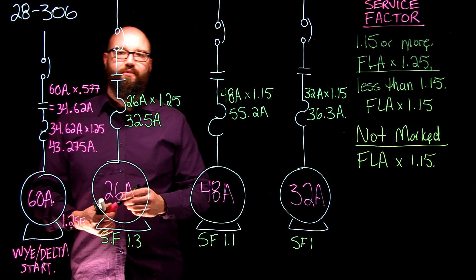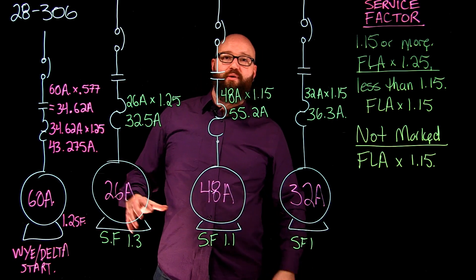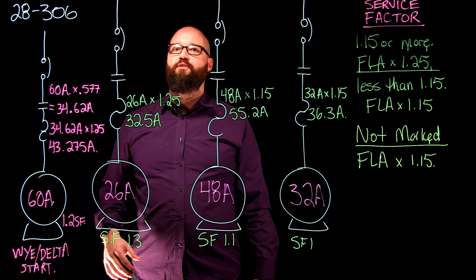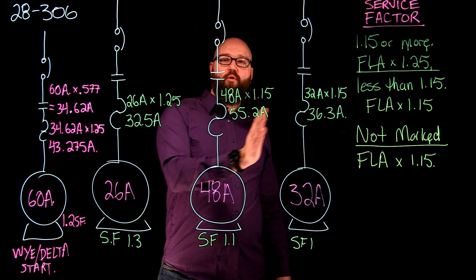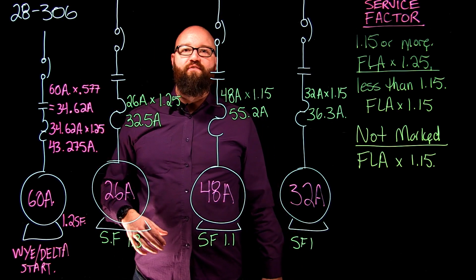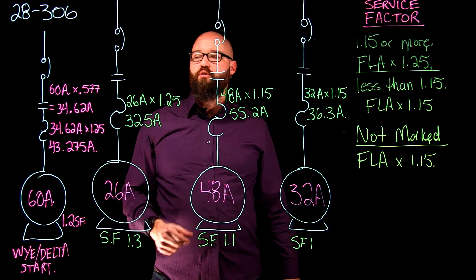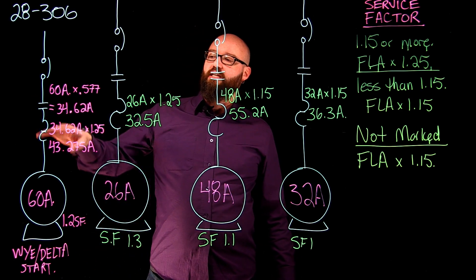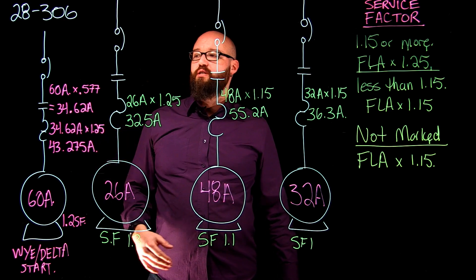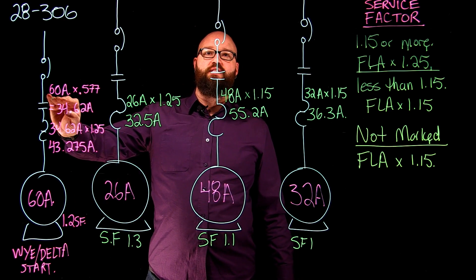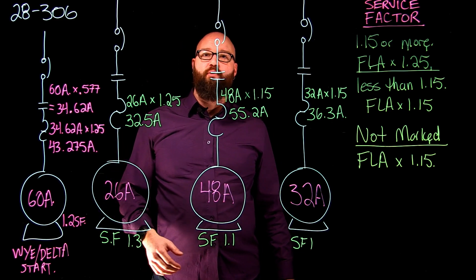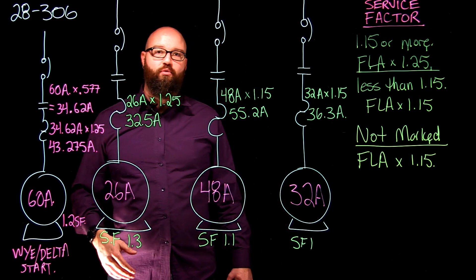So a little bit different on that one. But remember, if you are sizing the overload it must be off the phase current in that delta configuration. Our other three motors we're just using that straight FLA which is the line current to our motors, and again this one we're switching over to the phase current. Another way that we can get this root 3 smaller current is actually taking our line current of 60 amps and dividing it by root 3, or we can divide it by 1.732, which is the square root of 3 as well.